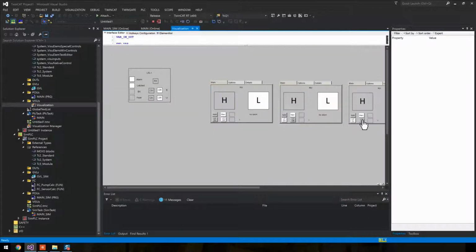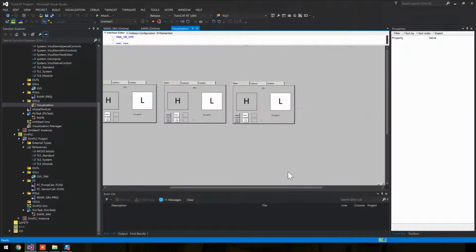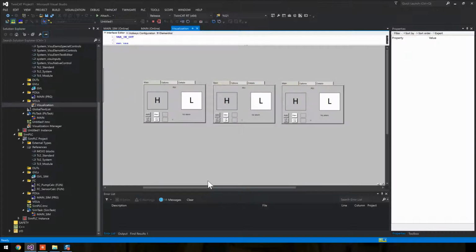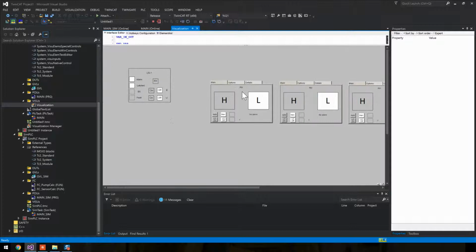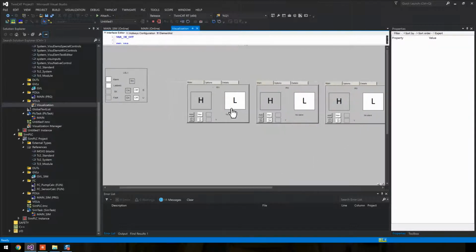So we've tested outside mode and manual mode. That is the manual mode, the buttons on the screen, and the outside mode, the buttons on the remote controller next to the pumps. And we tested the alarm with the safeguarding. So you have the basic function down. You're not allowed to run the pumps dry, and you can control it from the screen and from the local remote.